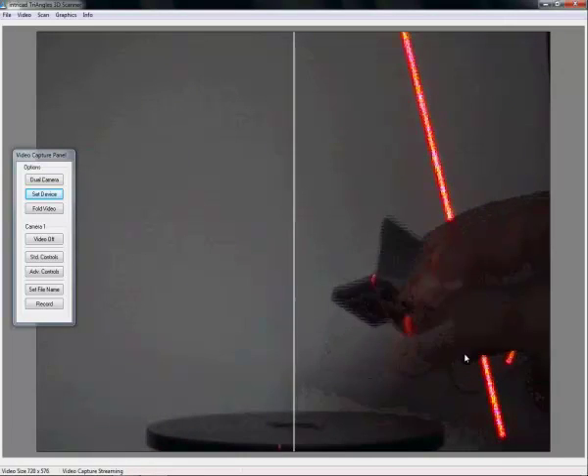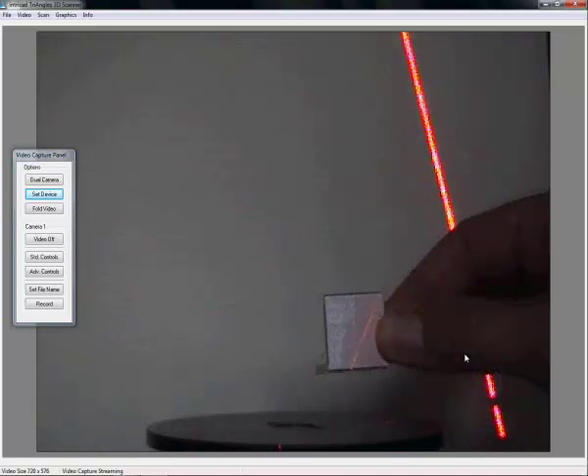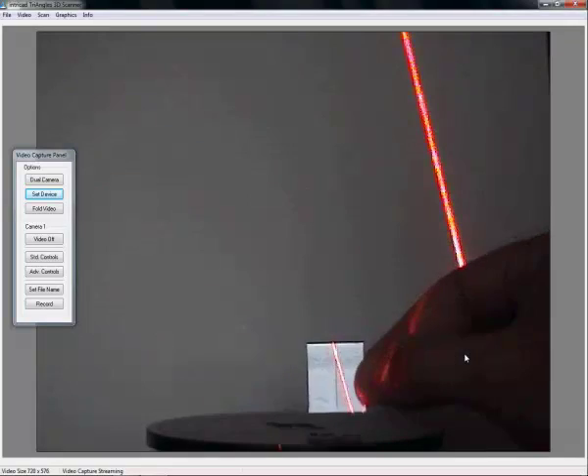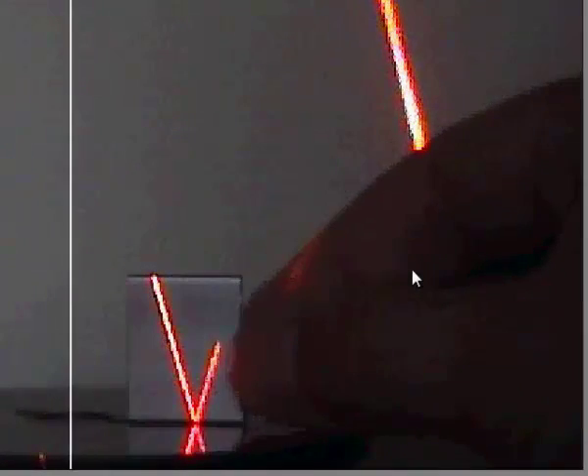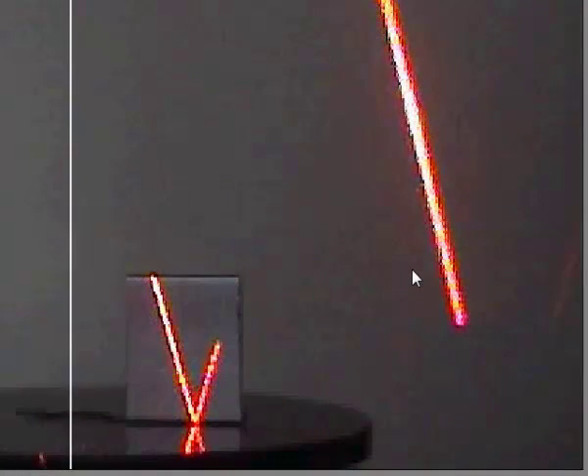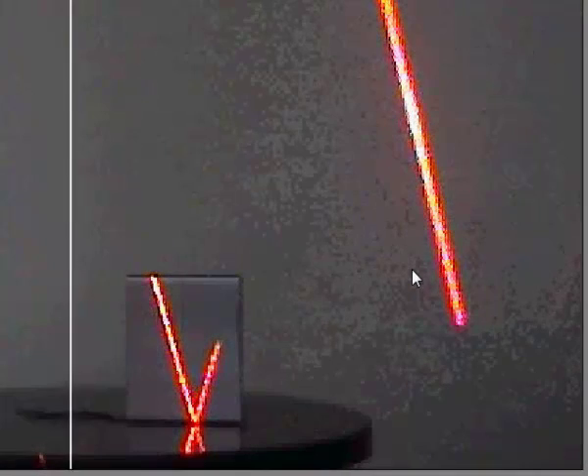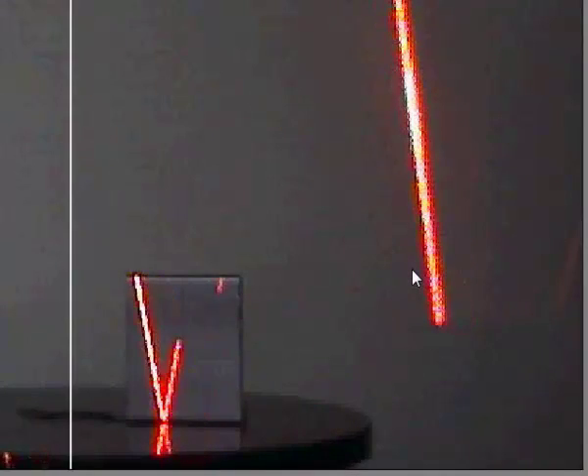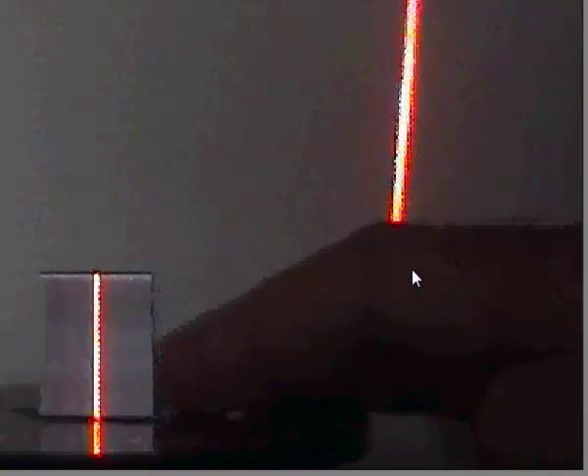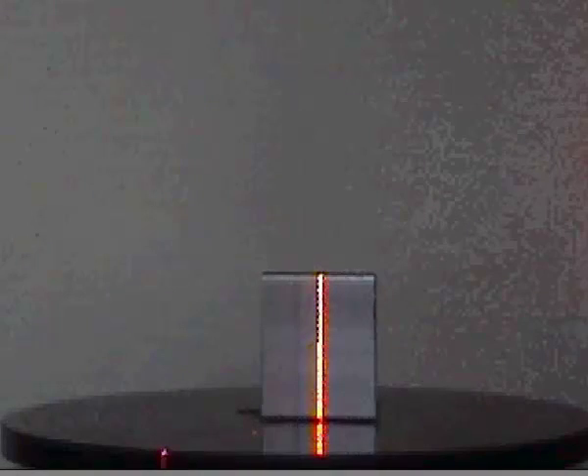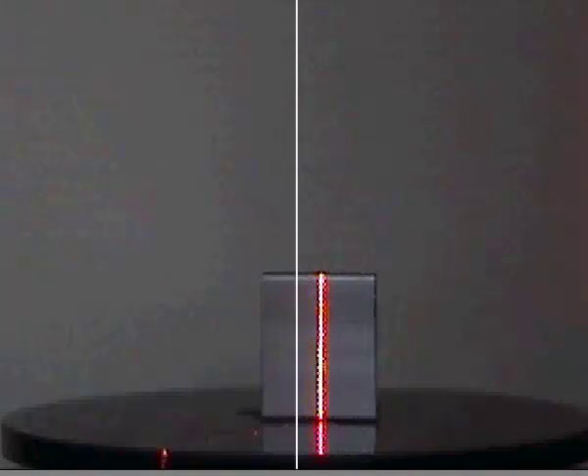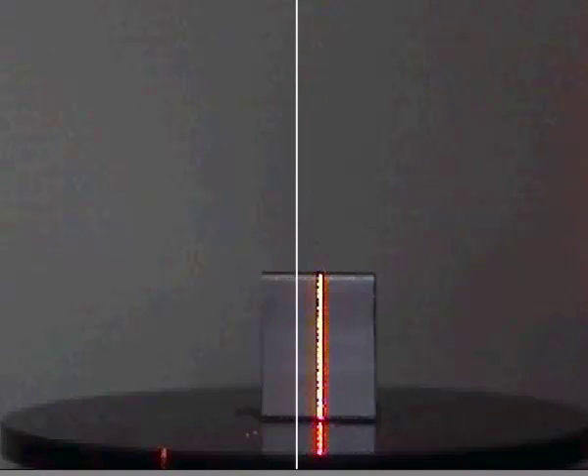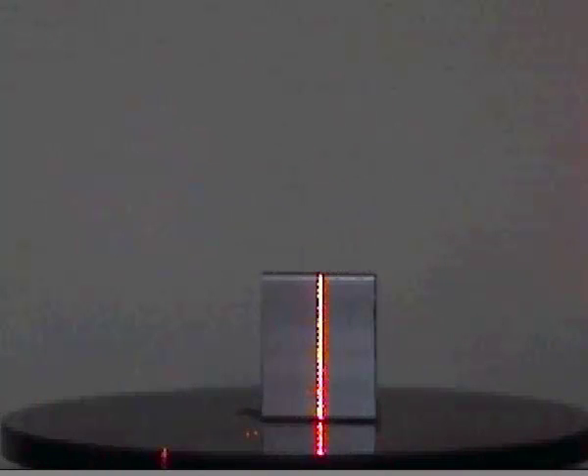In this particular case I am using a smaller version. Place the calibrator on the turntable in the laser line. And you will see a reflection shaped like a V. There, you can see it. We now have to rotate the complete laser assembly without changing the focus. Such a way that the V is completely overlapping itself and becomes a straight line. This is a bit tricky in the beginning. It might take a little while before you get this done correctly. But it's important that you do this as accurate as possible since the scan accuracy depends on this. This is about correct. You can see right now that the V has completely disappeared and moved into a straight line.